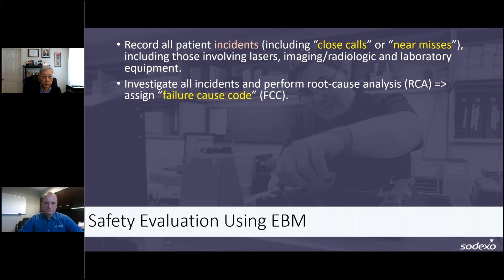Safety evaluation means that you have to look at all the patient incidents, and whenever possible, I would recommend that you include the close calls or near misses, because that will help you understand why something goes wrong and what you can do to reduce those risks. And then for every single one of these incidents, you should look at the cause of the failure, as Jason presented before, and assign a failure cause code. Okay. Then for the 4 special codes that are maintenance related, the service-induced failure, hidden failure, potential failure, and predictable and preventable failures, we need to go one step further, because now we're talking about incidents, so we cannot just assign a code and forget about it and just move on.